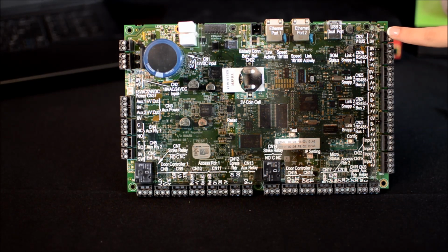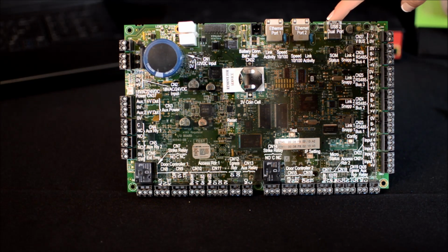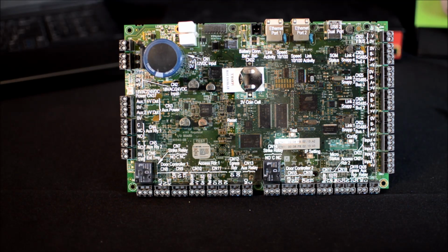At the top right-hand side of the panel, you will see the CN27 terminal block. This is designated as the V-bus, which is used for internal enclosure communications to additional modules. The functionality parameters of this bus require the wires not exceed the boundary of the enclosure in order to work properly. At the top right-hand side of the panel are 2 USB ports. These ports are designed to be used for panel firmware upgrades. They provide 200 mA of power and are not designed to power any external device.